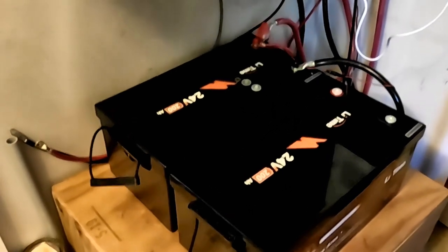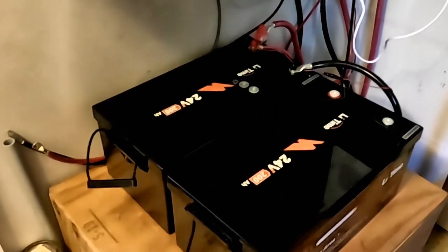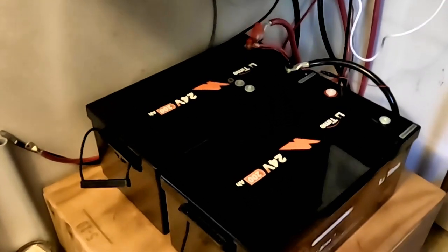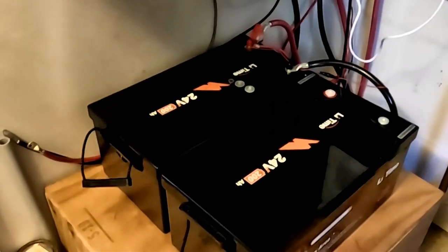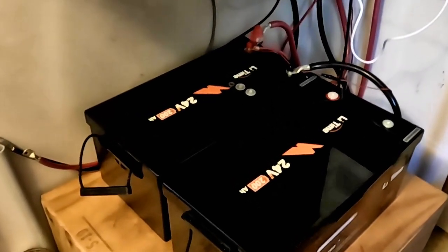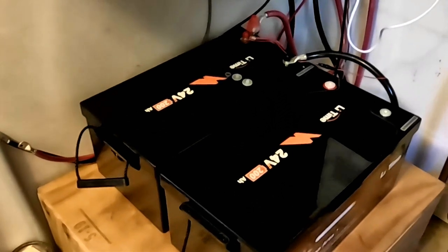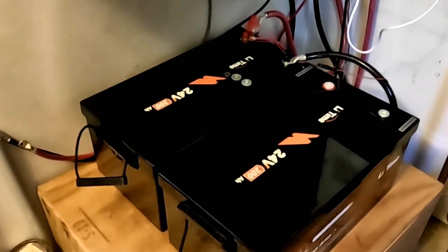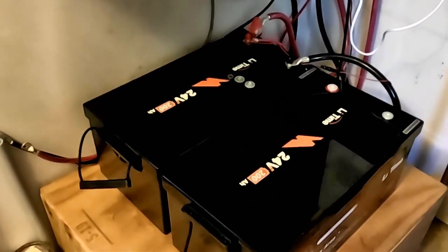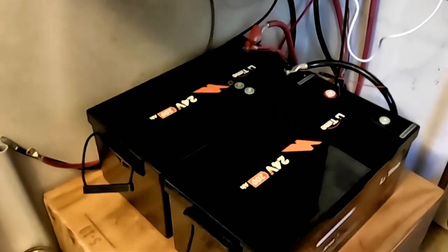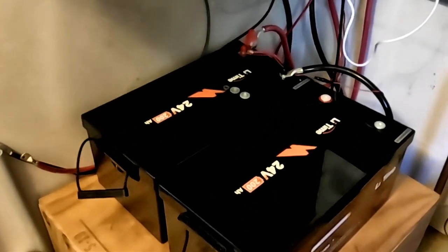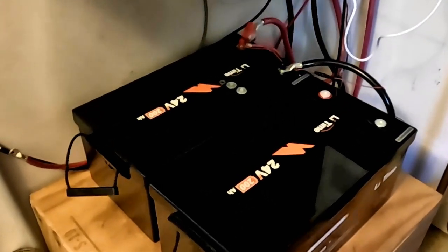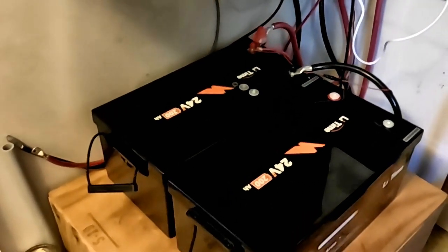Today, about 1:30, FedEx dropped these two batteries off. These are replacing the 10 kilowatt hours of lead acid batteries that I had. These two together are 10 kilowatt hours of lithium iron phosphate batteries. However, in contrast to the lead acid batteries which we really don't want to draw much below 50 percent of their capacity, you can draw these down to 100 percent of their capacity. So I can pull 10 kilowatt hours out of these two batteries.